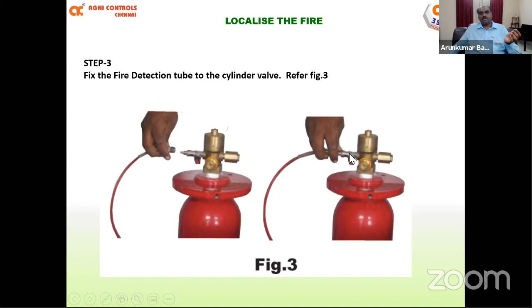And then we need to charge it. In the animation I have shown you, I open the ball valve and then the detection tube gets charged. So like this, we have to open the ball valve very slowly for the CO2 to fill the detection tube, and it will fill at a pressure of roughly between 15 to 20 bar.